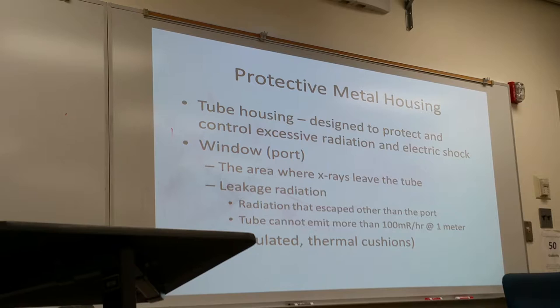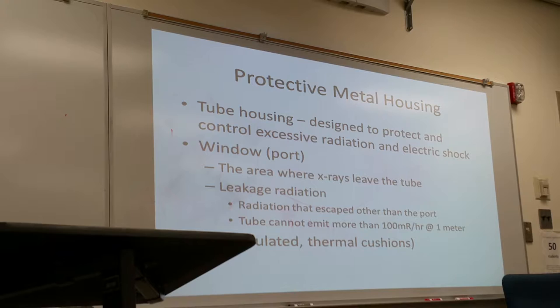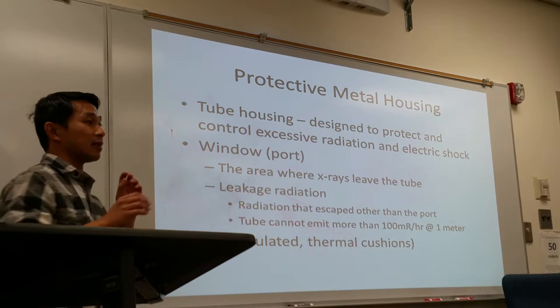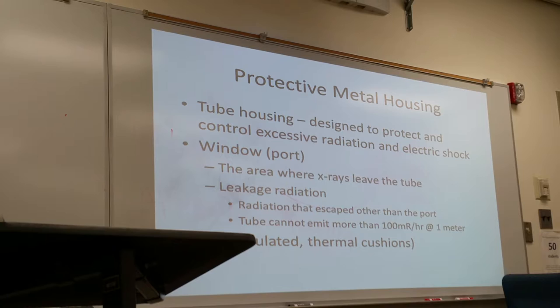The tube housing is designed to protect against excess radiation. The housing controls where the x-ray exits — the only part where a useful x-ray beam should come out is the window or port. Any x-ray exiting from a place other than the window or port is considered leakage radiation, and we don't want that.